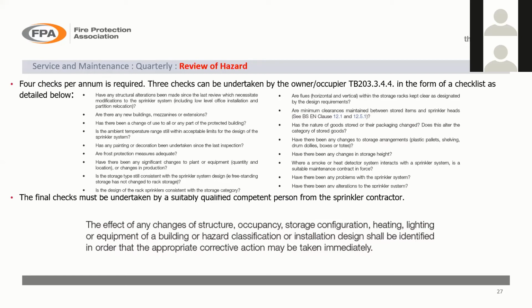So if you build a warehouse into your retail unit because you're storing lots of goods, you might be taking it from an ordinary hazard category into a high hazard. And somebody should be carrying out a hazard review just to look at this kind of thing and make sure that the system that you've got there still complies. Complies on a practical basis.